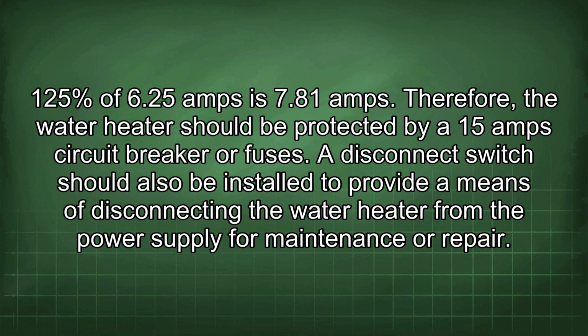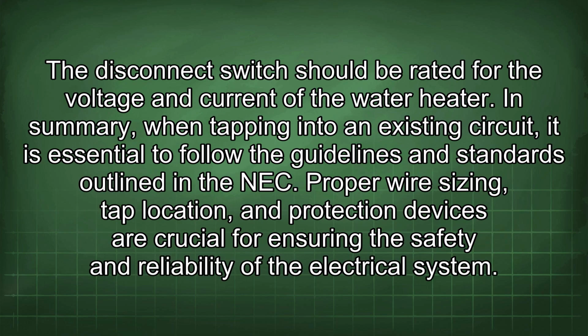125% of 6.25 amps is 7.81 amps. Therefore, the water heater should be protected by a 15 amp circuit breaker or fuses. A disconnect switch should also be installed to provide a means of disconnecting the water heater from the power supply for maintenance or repair. A disconnect switch should be rated for the voltage and current of the water heater.